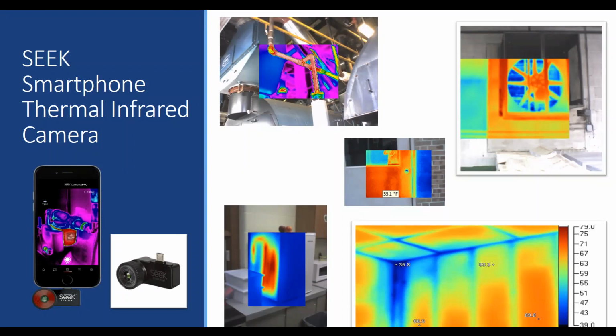In the photos, you can see we have used the infrared camera to see heat lost from uninsulated pipe insulation on piping. We can see that an interior door is being used instead of an exterior door, and therefore lacking in insulation. You can see the penetration leak, where the cool air is actually entering the building. And in the bottom left corner, you can see that a fridge appears to be overloaded and running inefficiently. Also in the bottom right photo, you can see a corner of the room has missing insulation. You would need to investigate more to determine the root cause, but you have discovered a problem and now you can move forward to correct it.